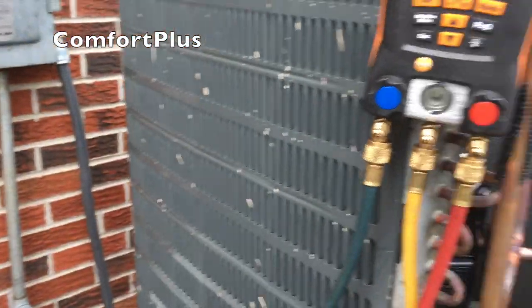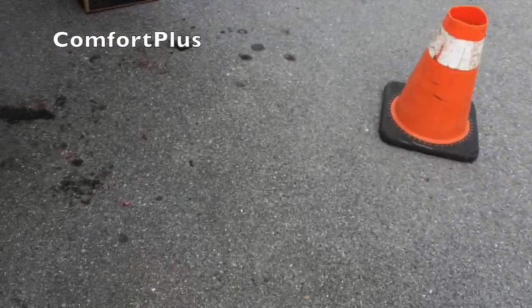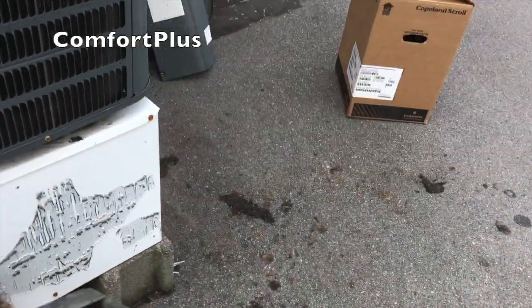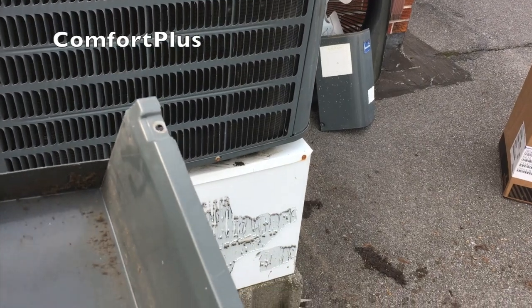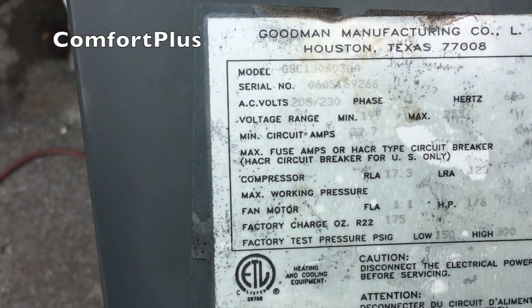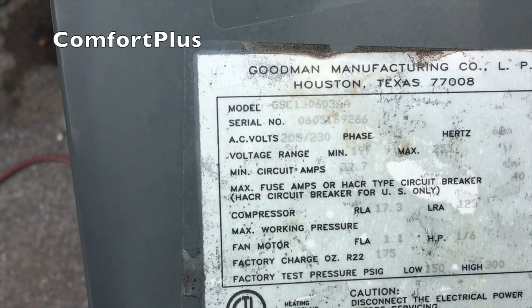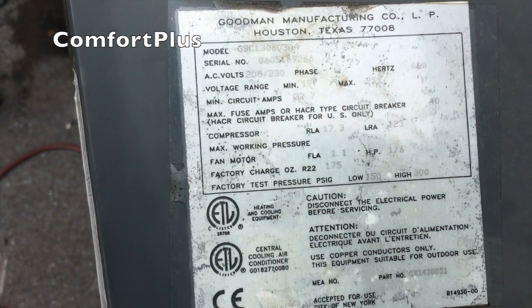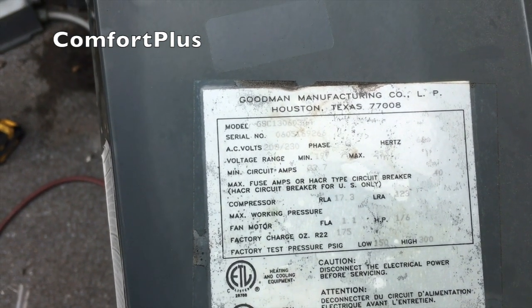So I started putting the panels back on. I got to thinking about that compressor and wondered if maybe this was a single phase unit and whoever converted it just put a 3-phase compressor in, and that's why it had a different year serial number, but actually this is a 3-phase unit. So it came that way. So I guess the compressor died within the first year.